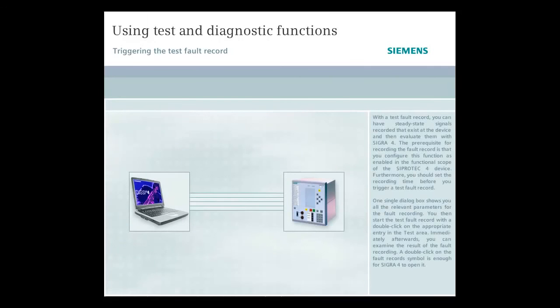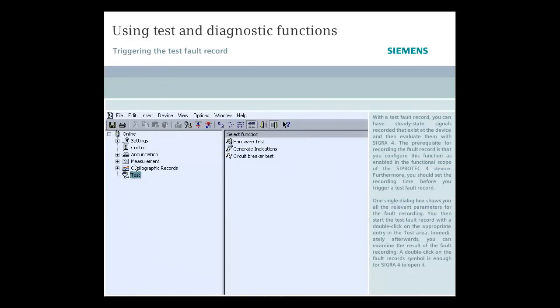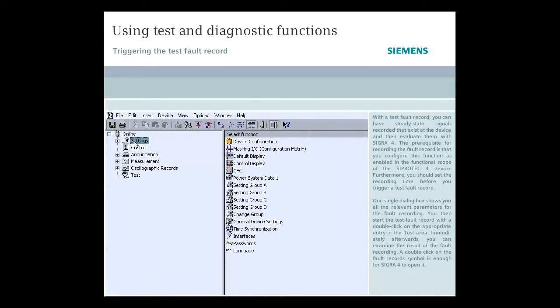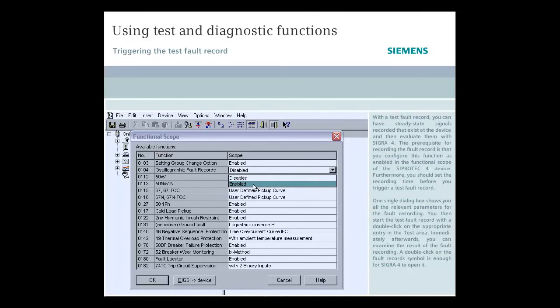With a test fault record, you can have steady-state signals recorded that exist at the device and then evaluate them with SIGRA 4. Furthermore, the prerequisite for recording the fault record is that you configure this function as enabled in the functional scope of the SIPROTEC 4 device.